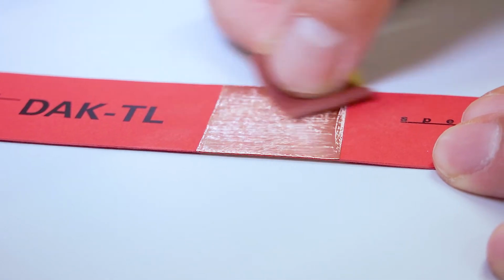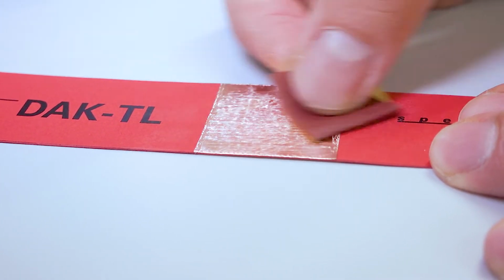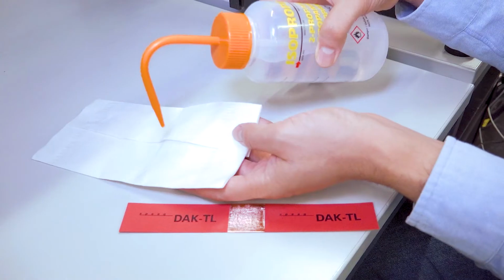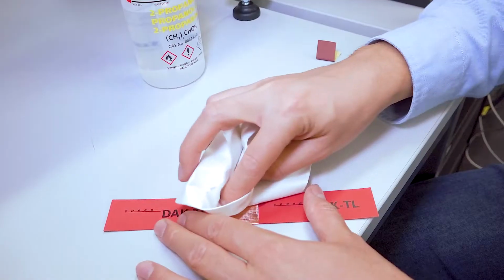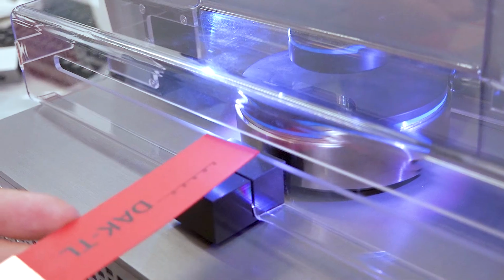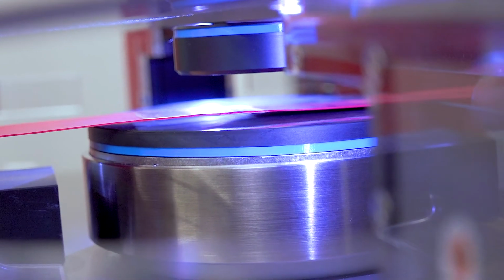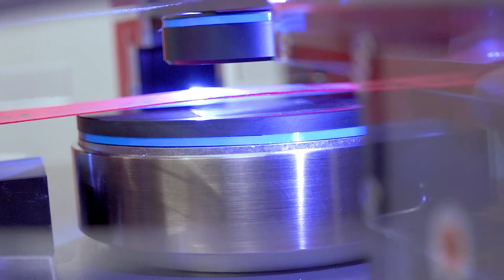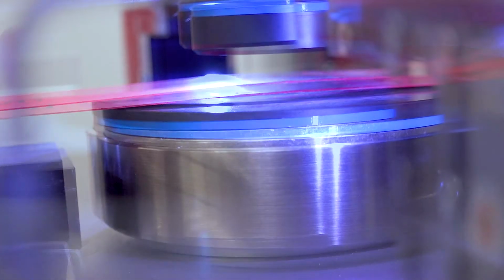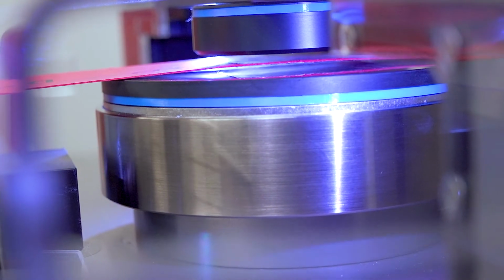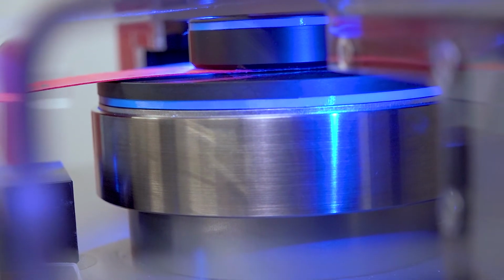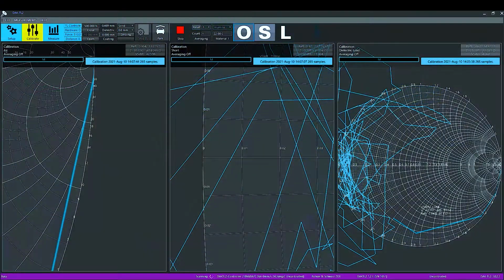Step 6. For an accurate and repeatable short measurement, I polish the copper tape with a fine sandpaper and clean the polished tape with isopropanol alcohol before use. I place the short tape on the lossy platform through the openings of the safety covers. I click on the Close button to bring the shorting tape to the probe with 500 Newton force to have a good contact with the probe.